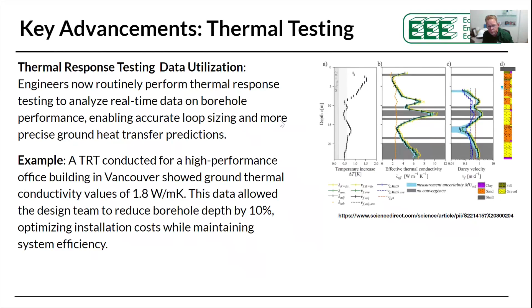Now, one of the other things that's come into play, and it's not that new, is we're seeing a lot of new grouting materials. To be clear, I'm not saying that if you use a high performance graphite enhanced grout, you should shorten your loop. What I'm saying is trust the math, do the calculations, figure out what your ground loop should or could be. But by using a thermally enhanced, like a graphite enhanced grout, you can have a significant impact on the performance of that ground loop. Just like if you don't backfill your ground loop correctly, you're going to have negative impacts on that ground loop as well. So materials have changed, and not just grouting materials.